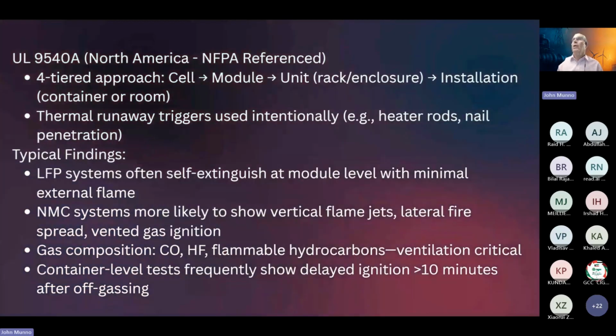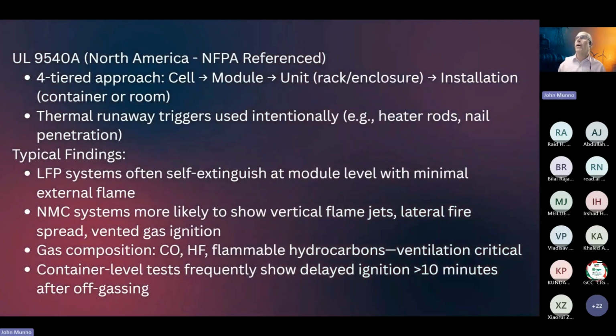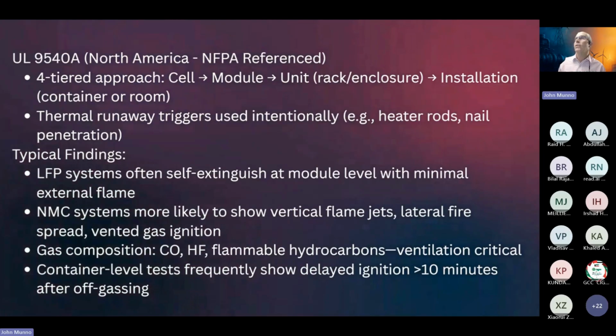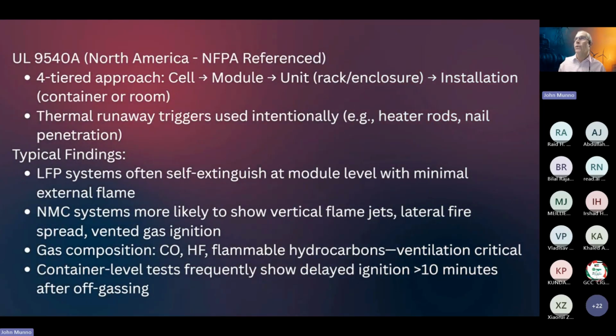All right. 9540A is North American based. It's a 4-tier approach. They first start the cell in thermal runaway, and they'll do that with heater rods or nail penetrations, sometimes torches. And they want to see, does it go to the module? And if it goes to the module, will it go to the next module? And so on. So it goes all the way up to, will it spread from container? So be careful. We'll talk about some of the things to watch out for when you have these test results.